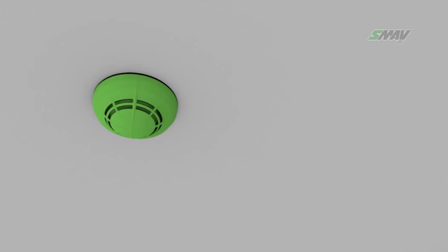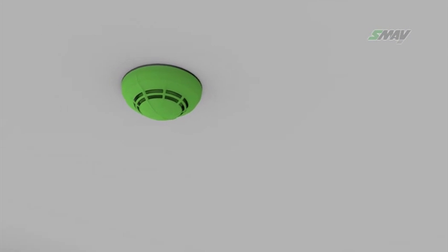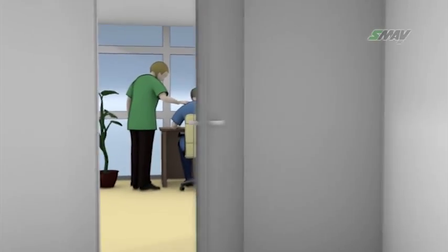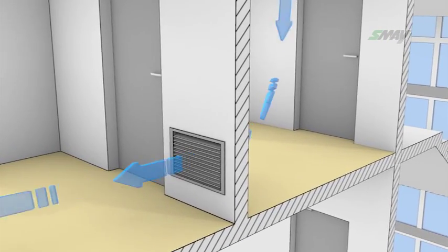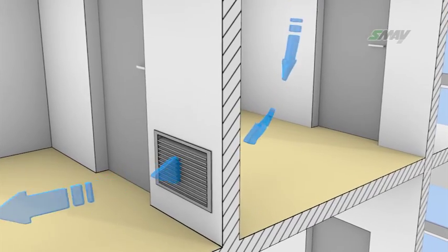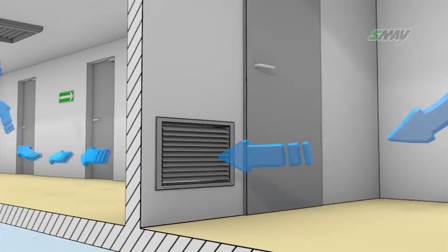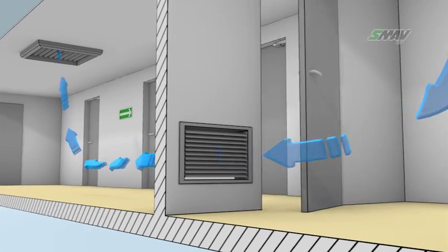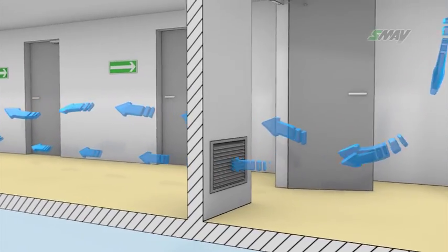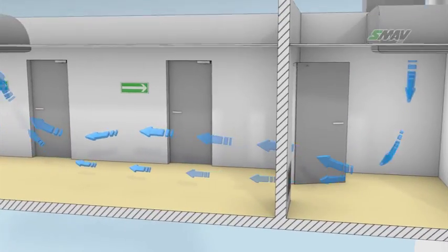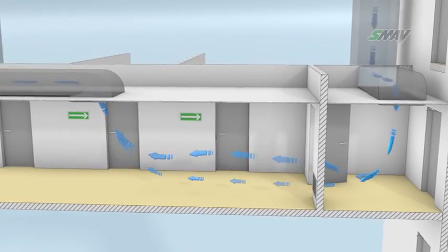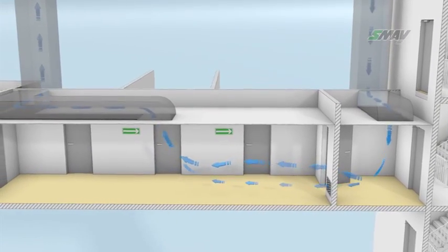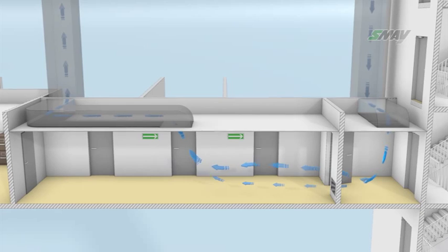The common solution is to supply compensation air to the firefighting lobby. In order to allow for the flow of air with the doors between the lobby and the corridor closed, an air transfer damper is installed in the wall dividing the aforementioned spaces. When the doors are opened, air flows from the lobby into the corridor, both through the door and the damper, ensuring that both the lobby and the stairwell used as an escape route are free of smoke.